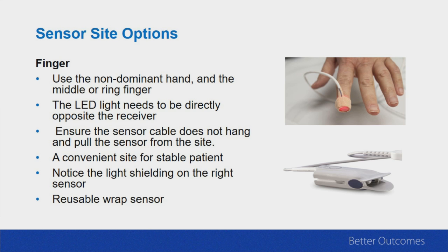Now, if you look at the non-disposable one at the bottom, you can see the gray plastic case on that. If you look where the finger would go into it, so if you're coming from the left side of your screen into that sensor and put your finger into that sensor, you'll notice that when it opens up, there's some white foam in there. That's the light shielding that we talk about to try to prevent room light from getting to that sensor. So that's built into that sensor.